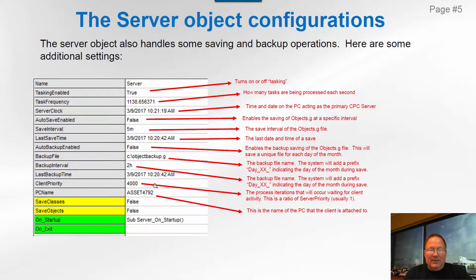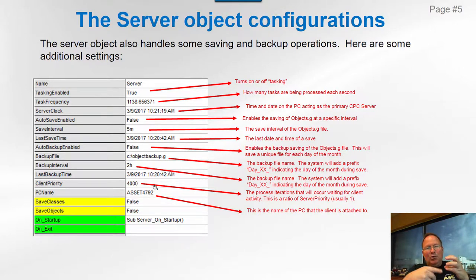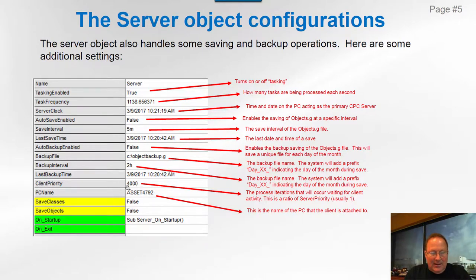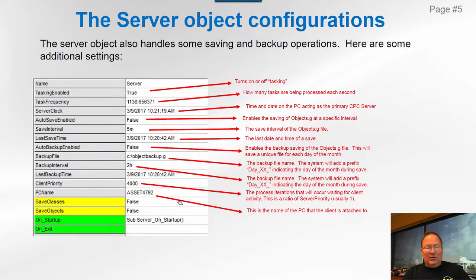Client priority is important. When the server starts addressing client interactions, it goes into a quick single for-next loop and stays there for this number of iterations before moving on back to tasker processing. The higher the value, the more time you're giving clients to grab information — it'll make clients more responsive, but it'll also slow down the server. The PC name is the name of the attached server PC. On startup is a quick script run when CPC server starts; on exit runs when you exit CPC.